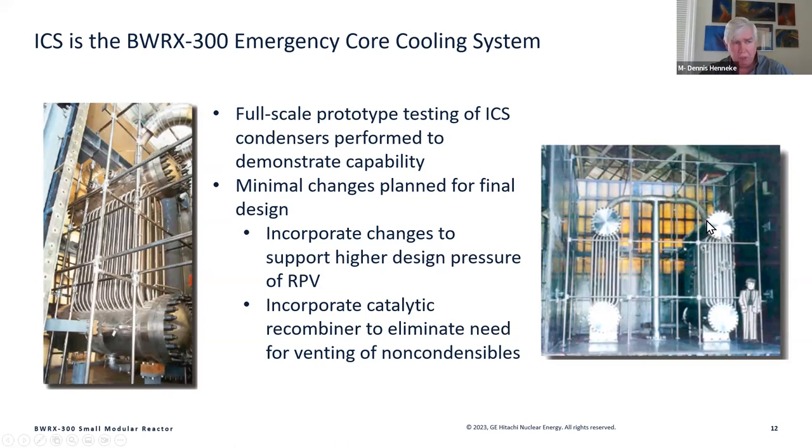The old ESBWR actually had a vent off the top of the isolation condensers, a vent off of non-condensable gas. In order to last for 7 days, we need to bottle up the isolation condensers and just hold everything within the primary.